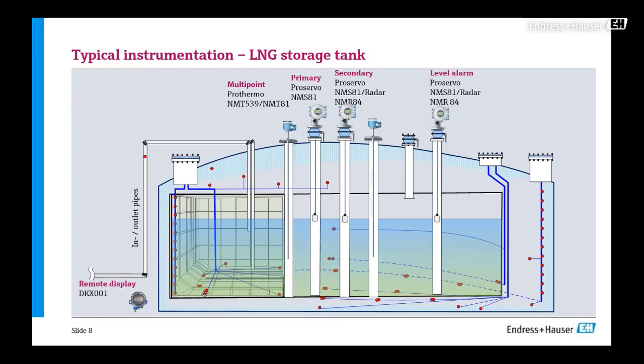The third gauge very often found in LNG storage is the level alarm. Here too we highly recommend using servo technology, and if diverse technology is required, you can also have radar. A typical combination you'll find in an LNG storage tank: primary servo with secondary radar and level alarm servo, or primary servo with secondary radar and radar as the alarm gauge. These are things you'll find in the configuration of instrumentation in a storage tank.